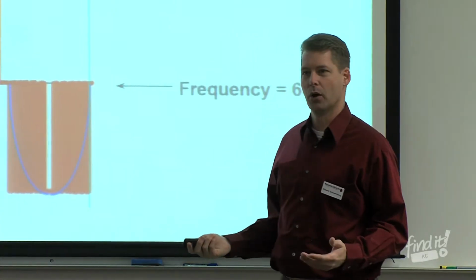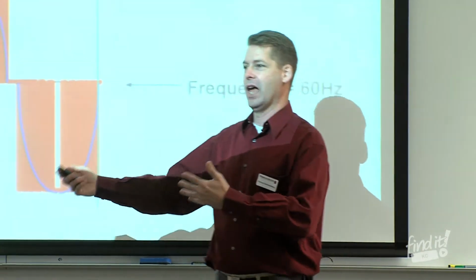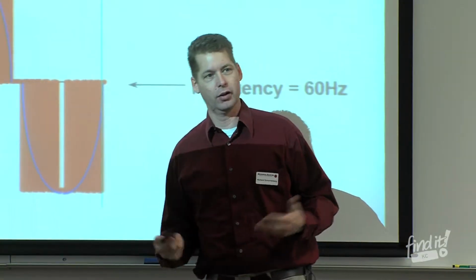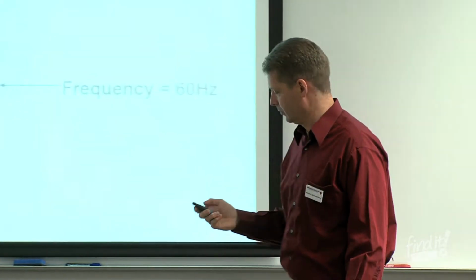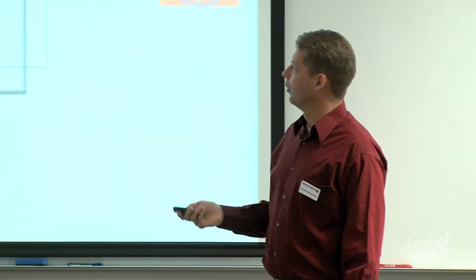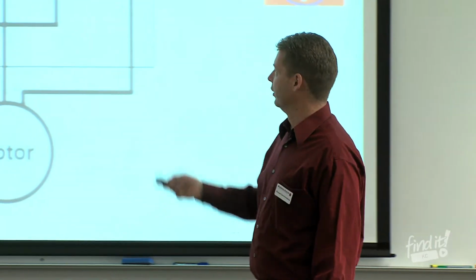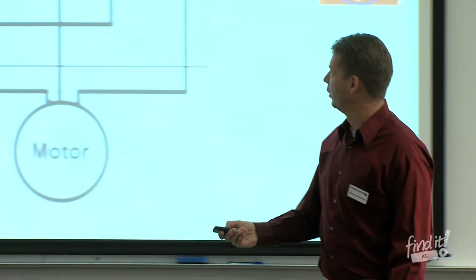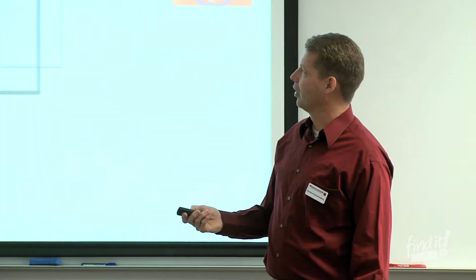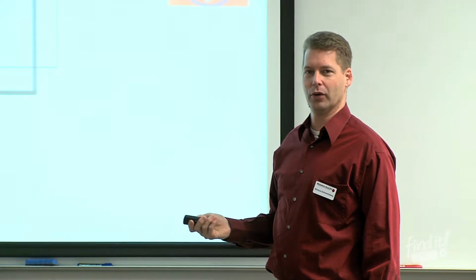By changing the speed the motor goes, we can actually affect the energy draw that the fan or the pump requires and save ourselves a bunch of electricity. So now take that from one switch and turn it into the 6 transistors to the 3 phase of the motor, and you end up with this fun little pattern of on again, off agains that send the power out to the motor, and it is the magic of how a VFD actually does its job.